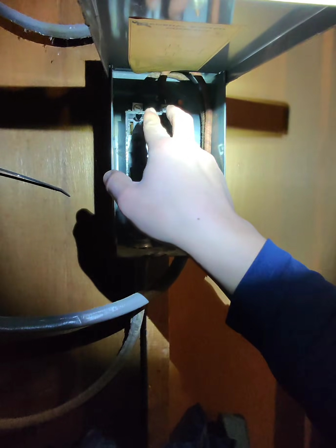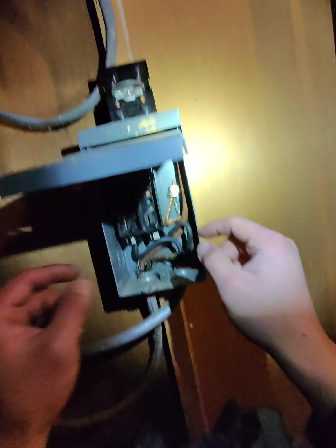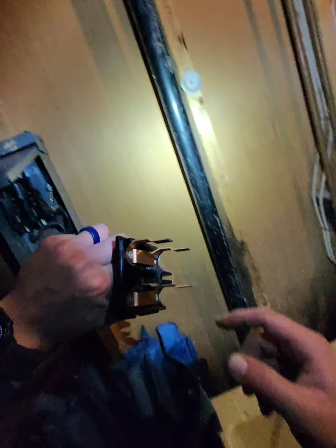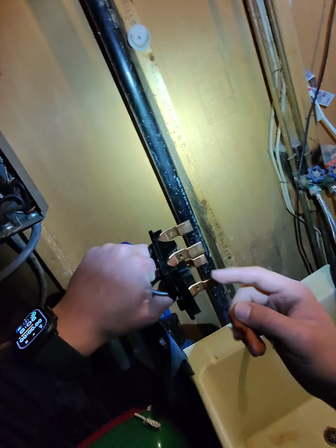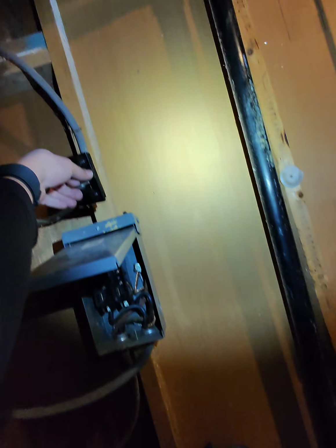This is from the circuit panel, and that's your 240 volts. It comes through here. Traditionally you have fuses, so this is called non-fused because it's just a metal piece, so there's no safety built into there. If there's an over-amp condition, it hits the circuit panel where the breaker will trip.